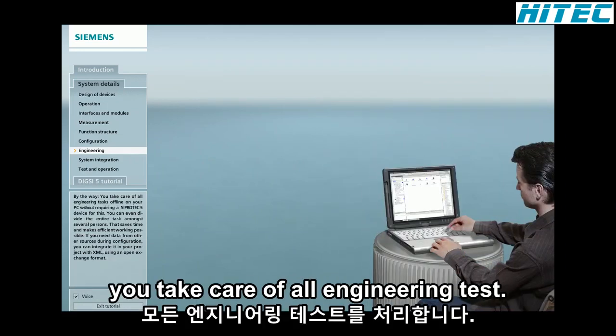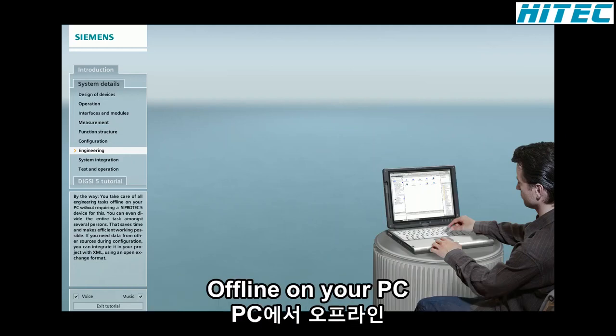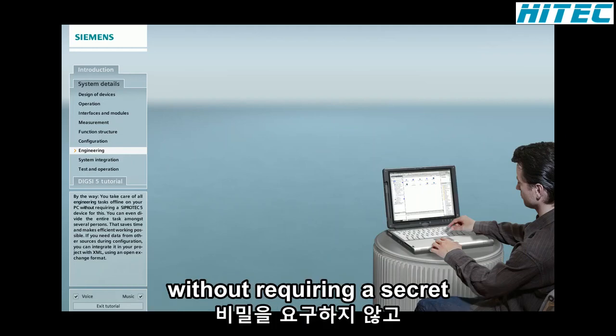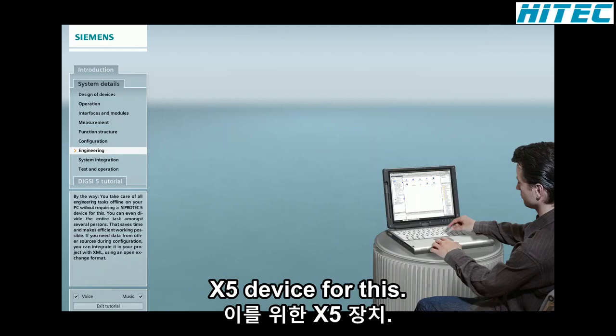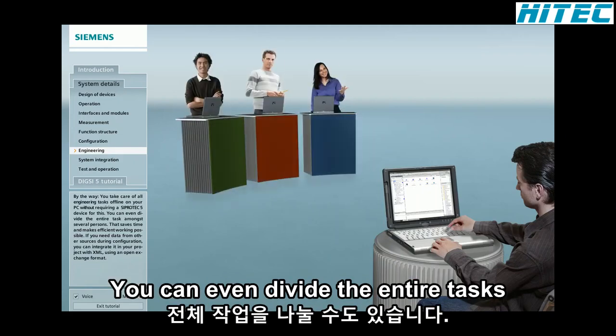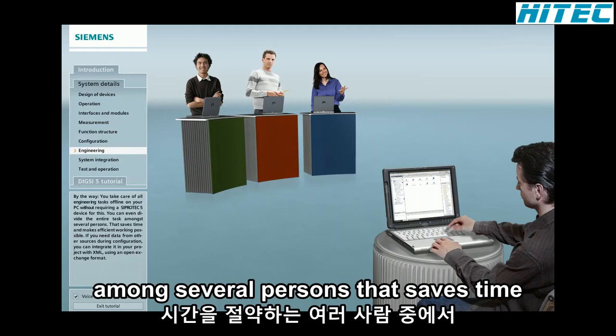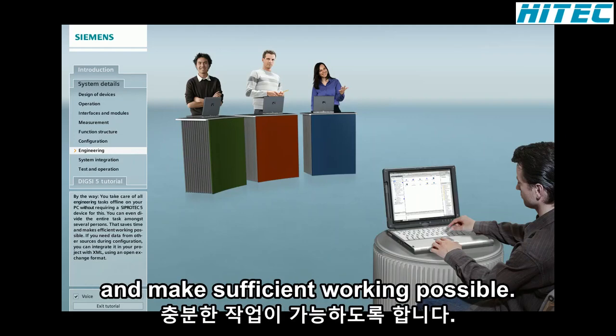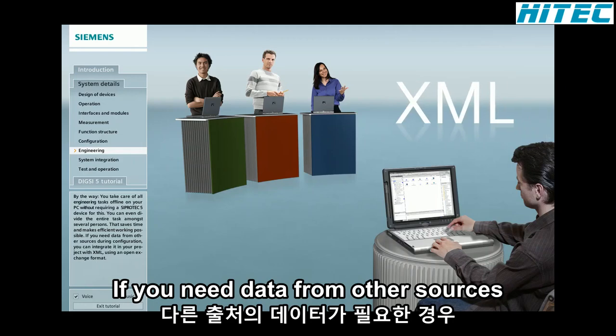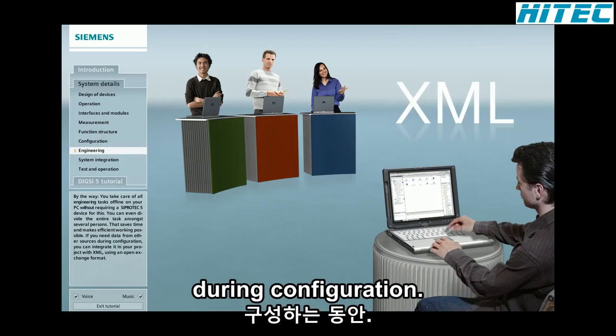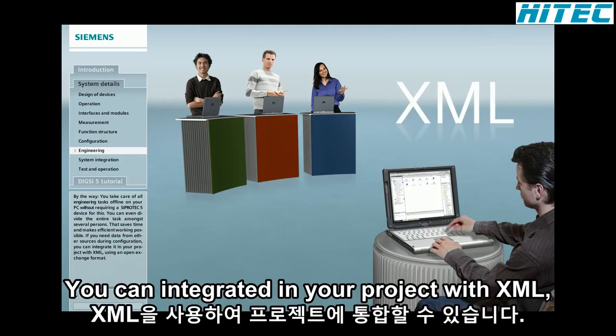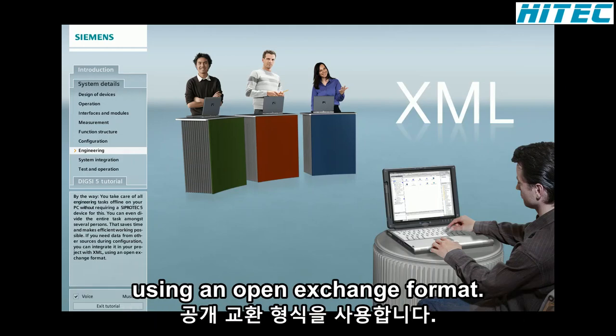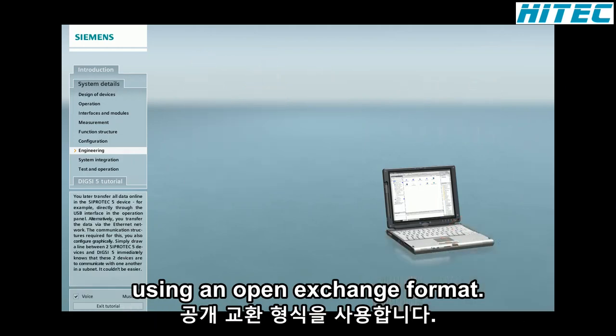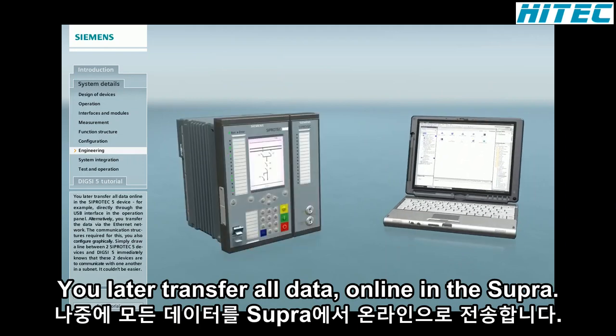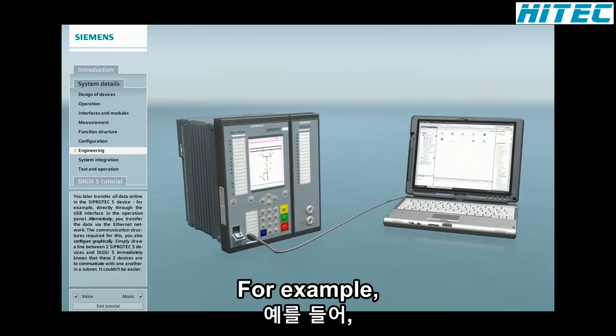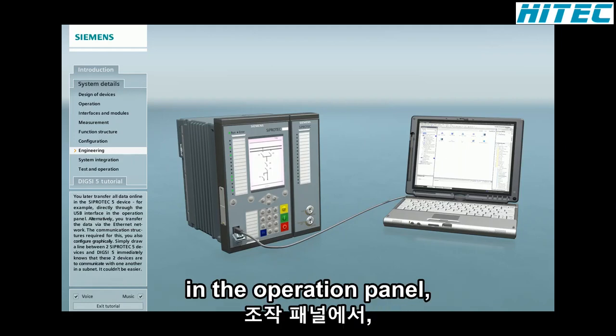By the way, you take care of all engineering tasks offline on your PC without requiring a SIPROTEC 5 device for this. You can even divide the entire task amongst several persons. That saves time and makes efficient working possible. If you need data from other sources during configuration, you can integrate it in your project with XML using an open exchange format. You later transfer all data online in the SIPROTEC 5 device, for example, directly through the USB interface in the operation panel.